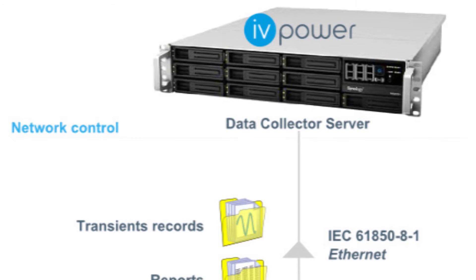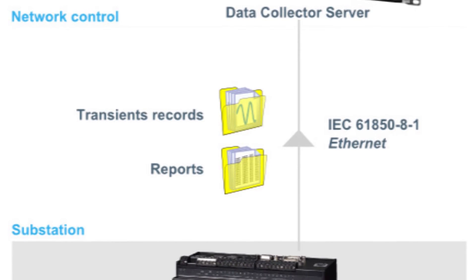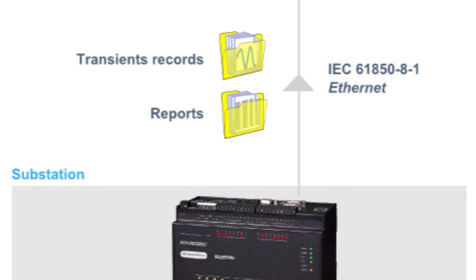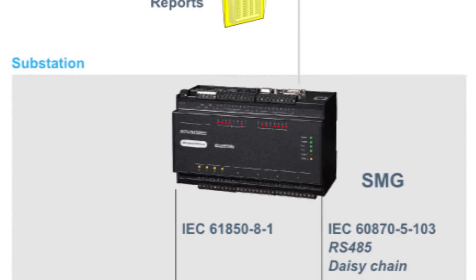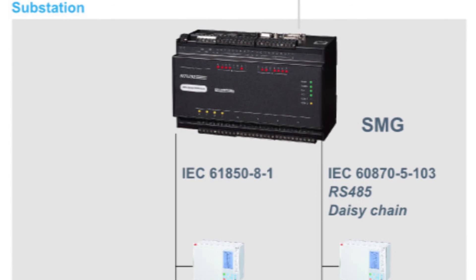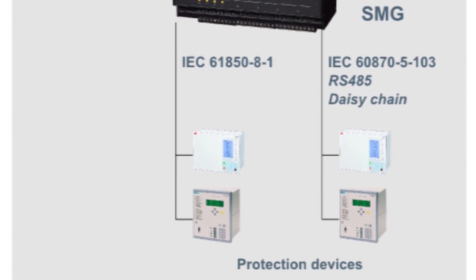You need to distinguish the communication protocols used within substations — like the 103 protocol, which is traditionally used in Europe and Asia — and IEC 61850, because nowadays modern substations are built with a redundant high-speed IEC 61850 bus. But this is inside the substation, and we usually don't touch this, especially for cyber security reasons — we leave all this communication within the substation.